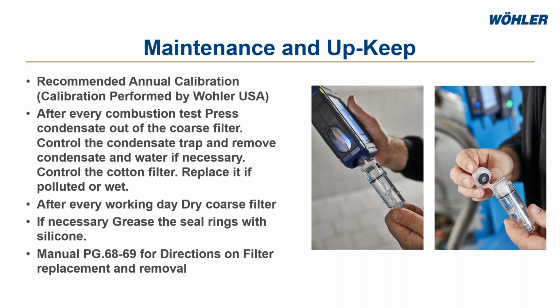So also too, we recommend greasing the seal rings, and really, that's not something that you should have to really do, but the point is, some of these O-rings and gaskets, it's really important that these stay intact. You want a tight seal around your water trap and your hose and probe assembly. That way you don't have any ambient air getting inside the sampling path of the probe in the analyzer. That would distort some of your readings. So it's important that you have a tight seal there.